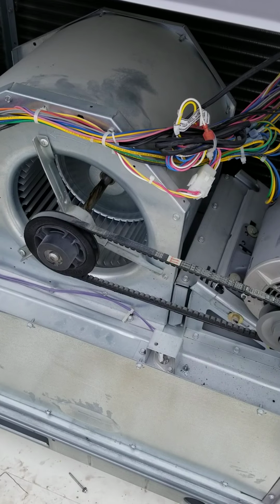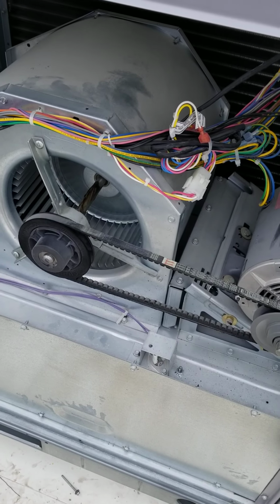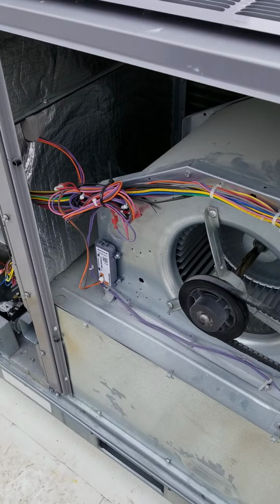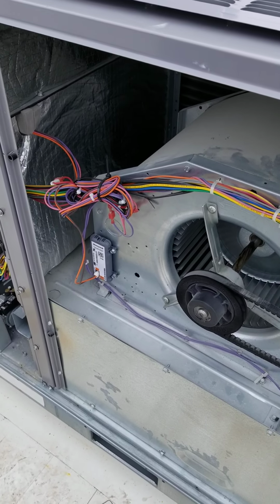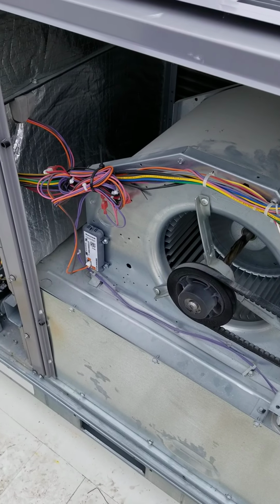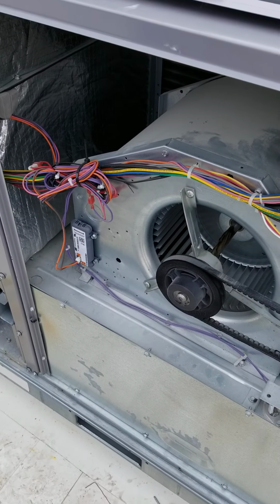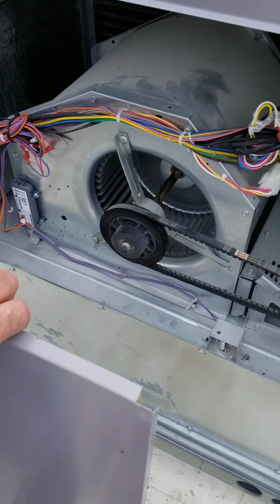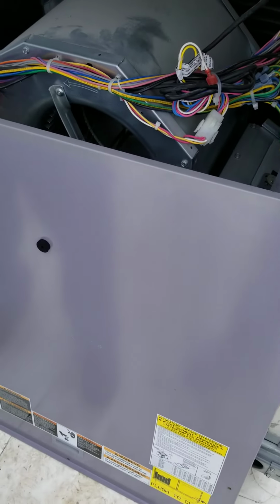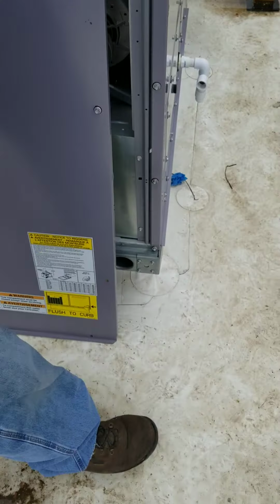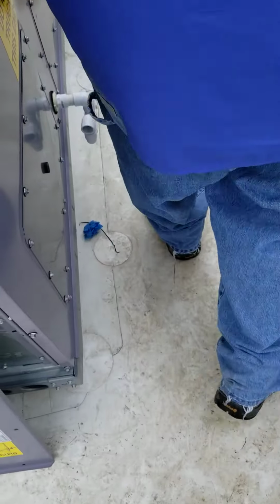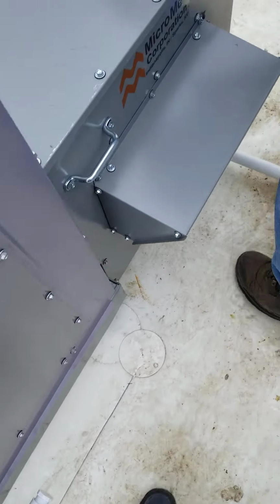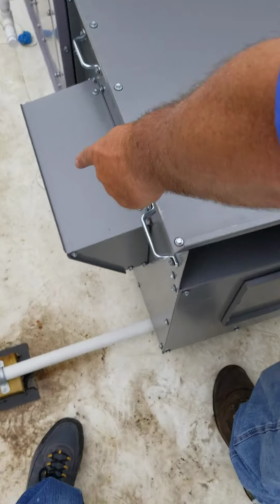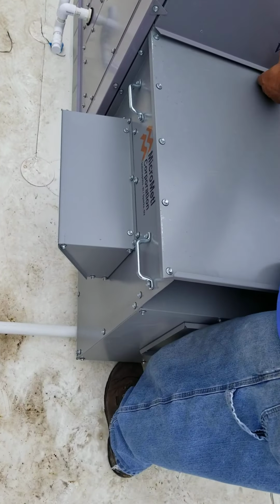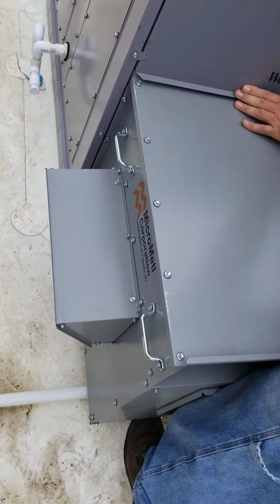Unless you economize. When you economize, there are two dampers: one opens to bring in outside air, and one closes off the return, exhausting the return air coming back from the space. The only other thing is where the filters are, same on both units. This is part of your economizer, the exhaust blower. If it ever comes on, it just blows air out on this side, and that's all return air from the building.